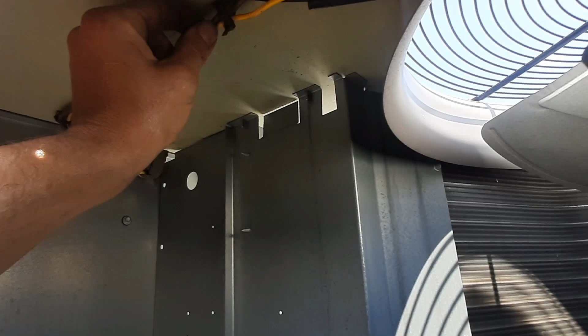I still need to go down and check to see if I got any fuses. I mean, they got the wires secured pretty good, and they got insulation there. I did check from the terminal block, main power that feeds all of these, and I still have no shorts, which I should have picked up from my contactor if I had a dead short. So I didn't pick up any shorts there. And capacitors are okay. So now I gotta figure out what the hell's going on.